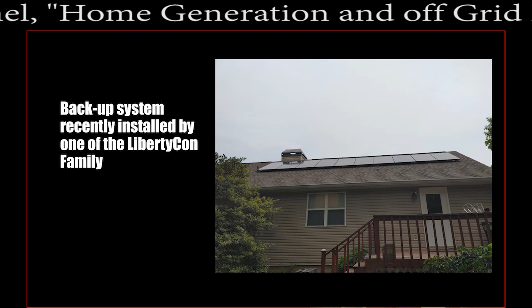We briefly mentioned having some type of transfer switch that they put in, and this is the transfer switch installed. Generac was the company that put this in — they're better known for gas backup systems than solar, but they're doing solar too. They have a very nice transfer panel that utilities like, because as long as there is live power on the transmission or distribution line coming to your house, this system will not allow you to transfer your load to your backup system. Or if it does, it opens a breaker connected to the utility side and disconnects the utility.